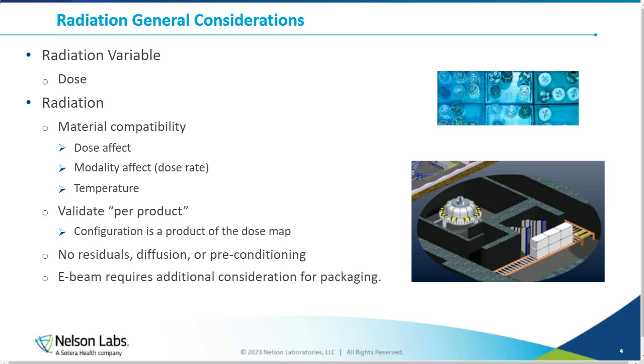So that modality difference, that dose rate difference, is that gamma is generally going to be over the course of hours in order to receive a full sterilization dose, whereas with electron beam, we're dosing in minutes to even seconds. So anytime we're doing sterilization, we're essentially adding energy into the system. For ethylene oxide, that's chemical energy. For radiation, that's ionizing radiation. And anytime we're putting energy into the system, that's going to affect product. If we're doing it for gamma, that's over the course of hours, and for E-beam, that's over the course of minutes and seconds, so that's going to be a difference in energy input.